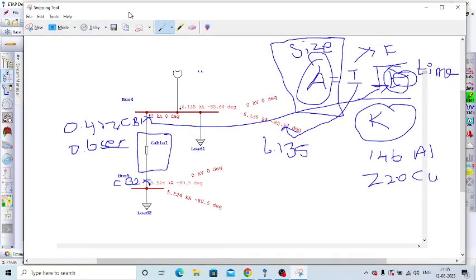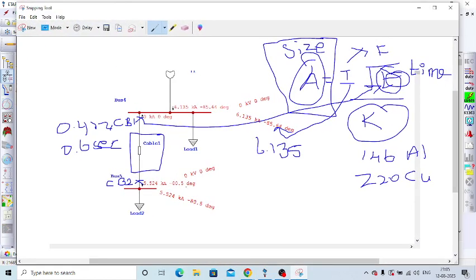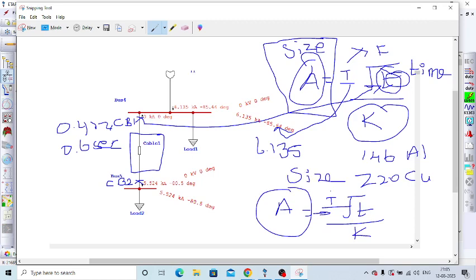Okay, so I hope you all understand how the cable selection has been done. Several criteria are there. One of the criteria is that the cable has to withstand the fault current flowing through it. So this is the formula: A equals I into root T divided by K. A is the size, I is the fault current in ampere, T is the breaker operating time, K is the constant for the cable material. I hope you are clear.